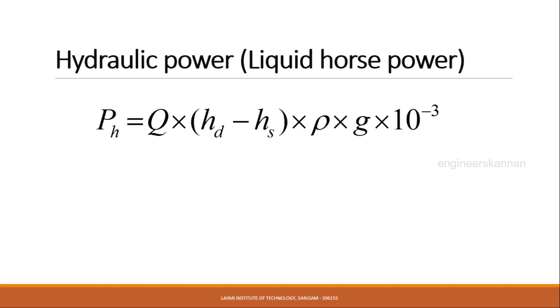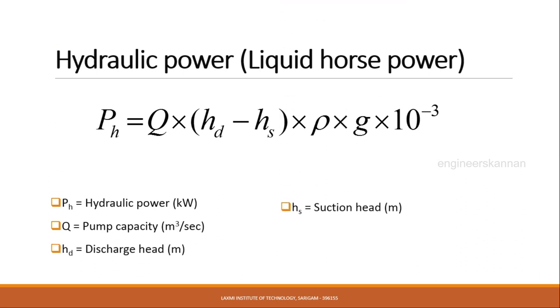P_h equals Q times (h_d minus h_s) times rho times g times 10^-3, where P_h is hydraulic power in kilowatts, Q equals pump capacity, h_d and h_s are the discharge head and suction head in meters, rho equals density of the particular fluid, and g equals acceleration due to gravity.